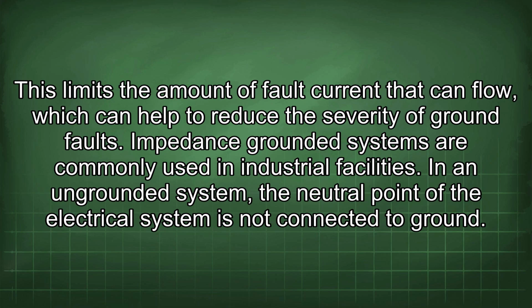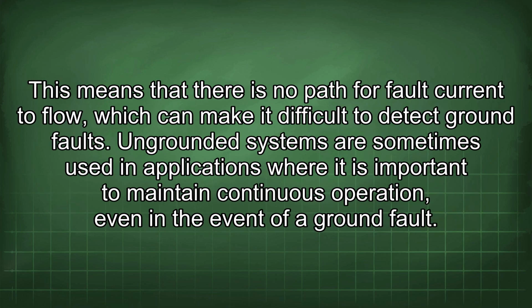In an ungrounded system, the neutral point of the electrical system is not connected to ground. This means that there is no path for fault current to flow, which can make it difficult to detect ground faults.